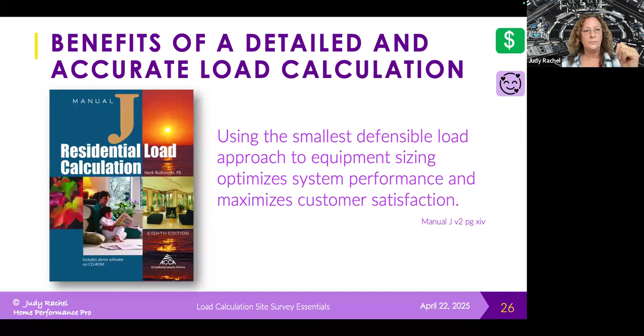And we're given parameters. It depends on what type of equipment, whether we're using furnaces and AC or whether we're using heat pumps or multi-stage equipment. But basically, it's about plus or minus 10% of the equipment that we're choosing. We can't get equipment in every single size. And so that's why we have to look at the load calculation, look at our performance data from the manufacturers, and match it as best as we can.